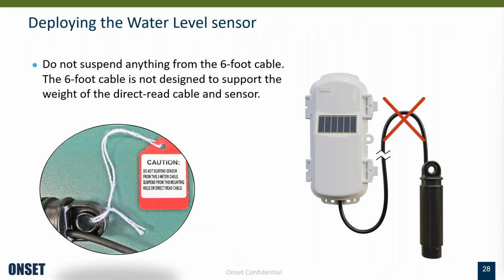Another thing: the device on the top end ships with a 1.8 meter cable, meant as a means to communicate between the direct read side and the mote side. This cable should not bear any weight—it should not be used to suspend your water level sensor. We ship it with a tag noting this, and it's all documented.